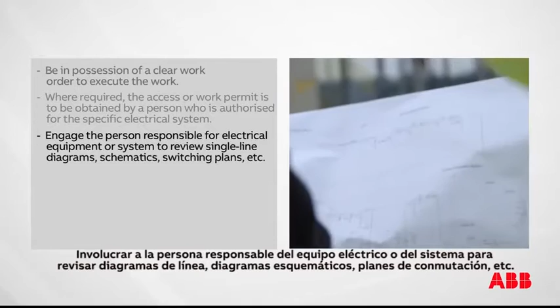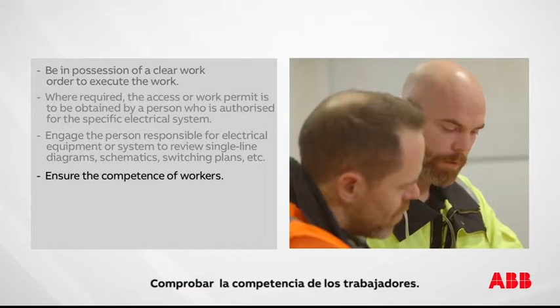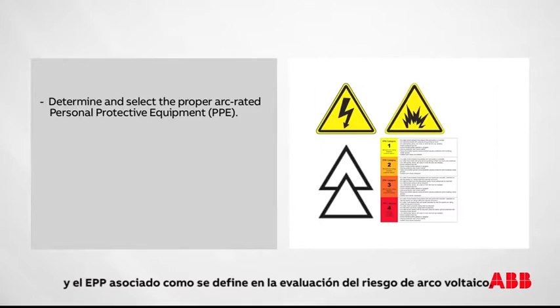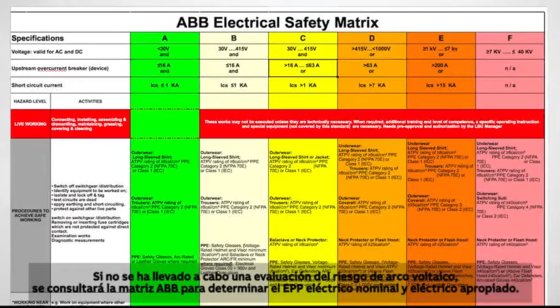Engage the person responsible for electrical equipment or system to review single-line diagrams, schematics and switching plans. Ensure the competence of workers. Check for proper tools for the job. Determine and select the proper ARC-rated personal protective equipment, PPE, and associated PPE as defined in the ARC Flash risk assessment. If an ARC Flash risk assessment has not been conducted, then the ABB matrix shall be consulted to determine the appropriate ARC-rated and electrical PPE. Finally, decide on the appropriate work methods and initiate the permit to work process.